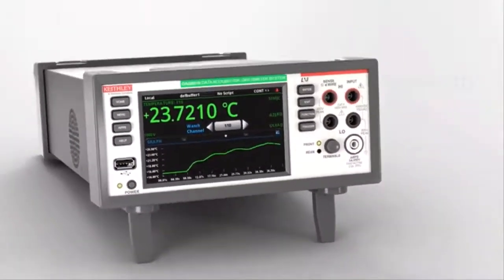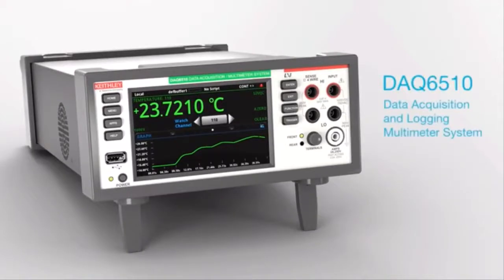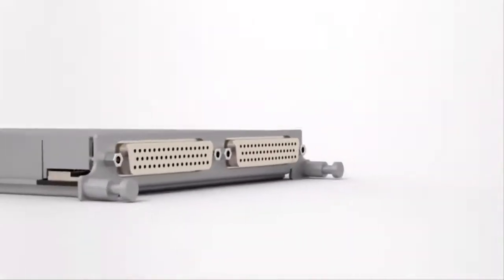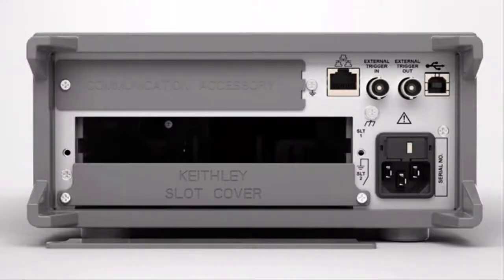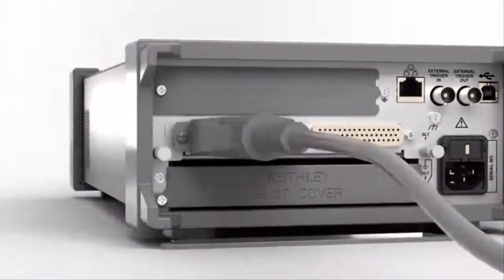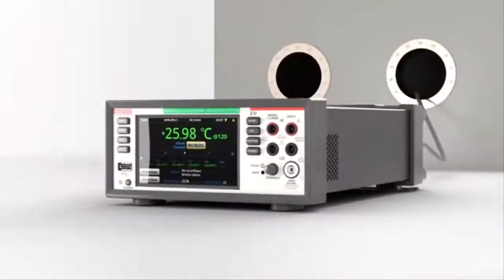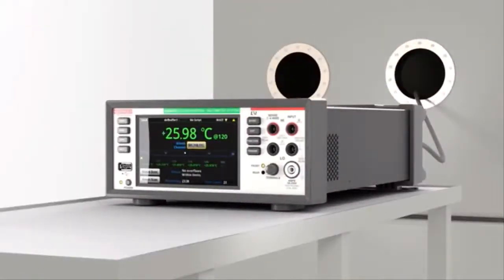The Keithley 6510 is an incredible device for long-running tests. It allows you to set up scans, trigger models, and other automation to do complicated, high channel count test and data logging. In this demo, we're going to connect to 2 temperature channels on the 6510 and monitor them continuously as you might in an environmental chamber test.